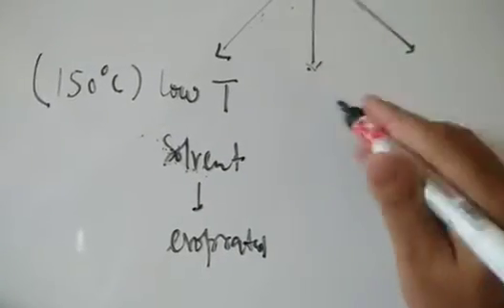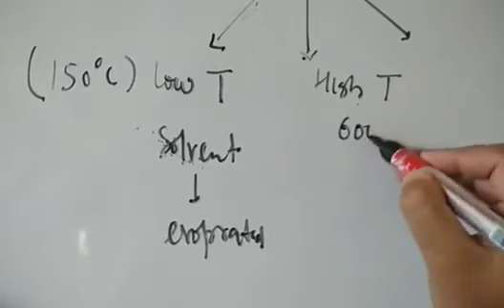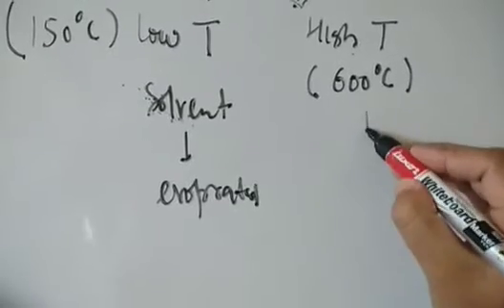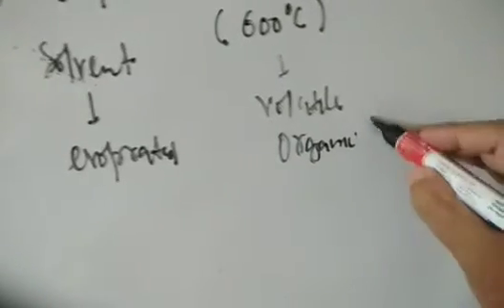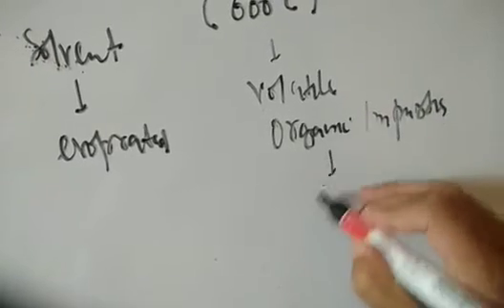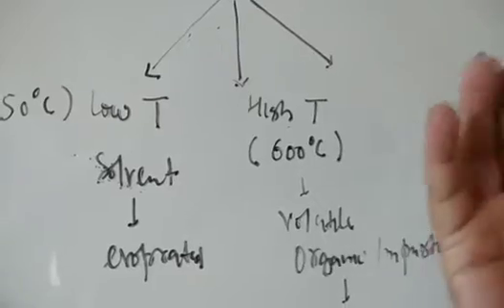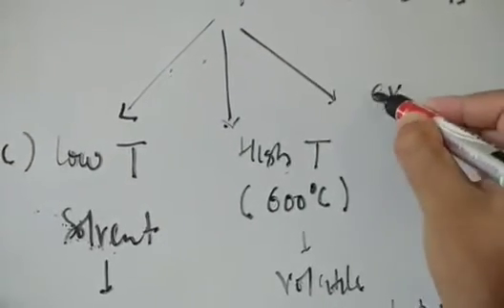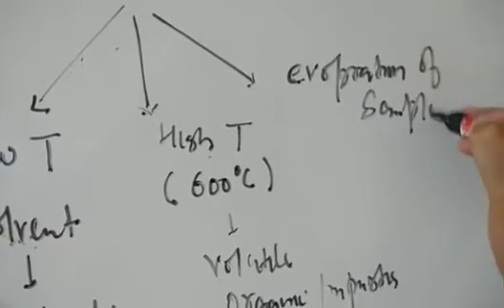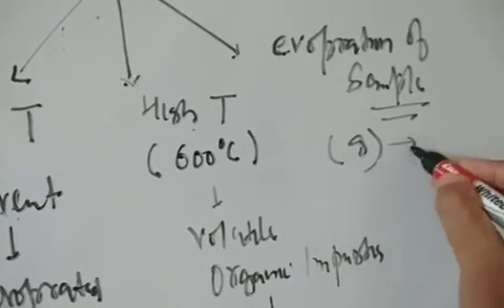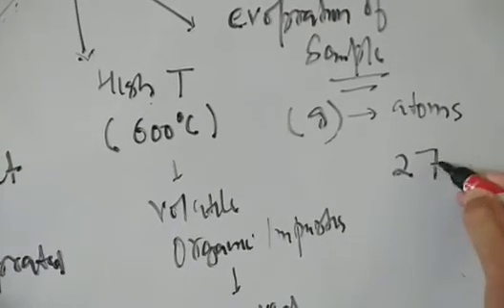Step number two: at a slightly higher temperature, around 600 degrees, what happens is that volatile organic materials — organic impurities or compounds — get removed. Step number three: the sample gets evaporated and converted into the gaseous state. Once it gets evaporated, the gas absorbs the heat and gets converted into atoms. This is the final state and here the temperature is very high — 2700 degrees.